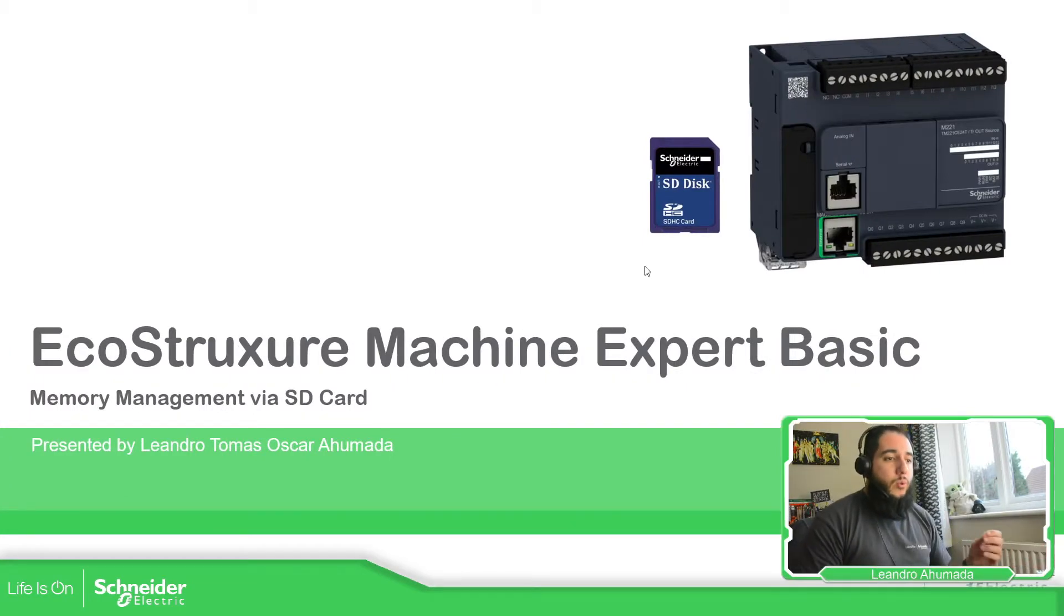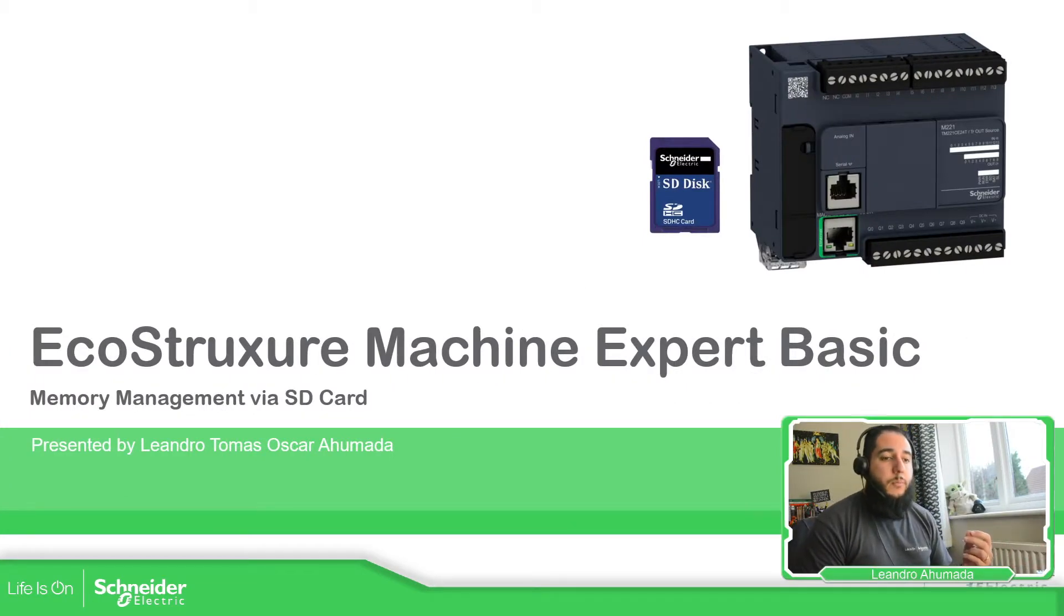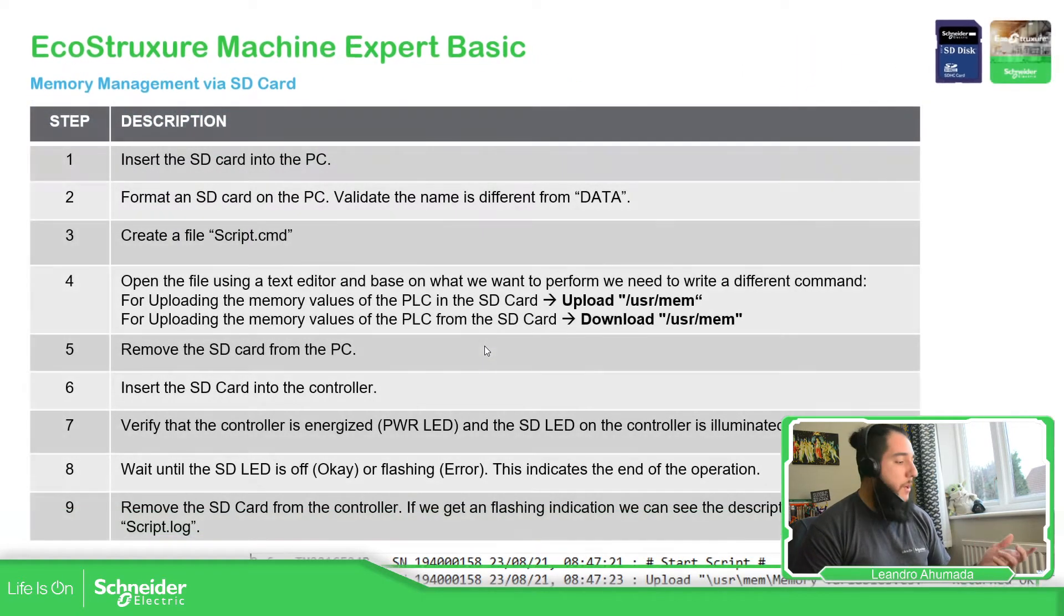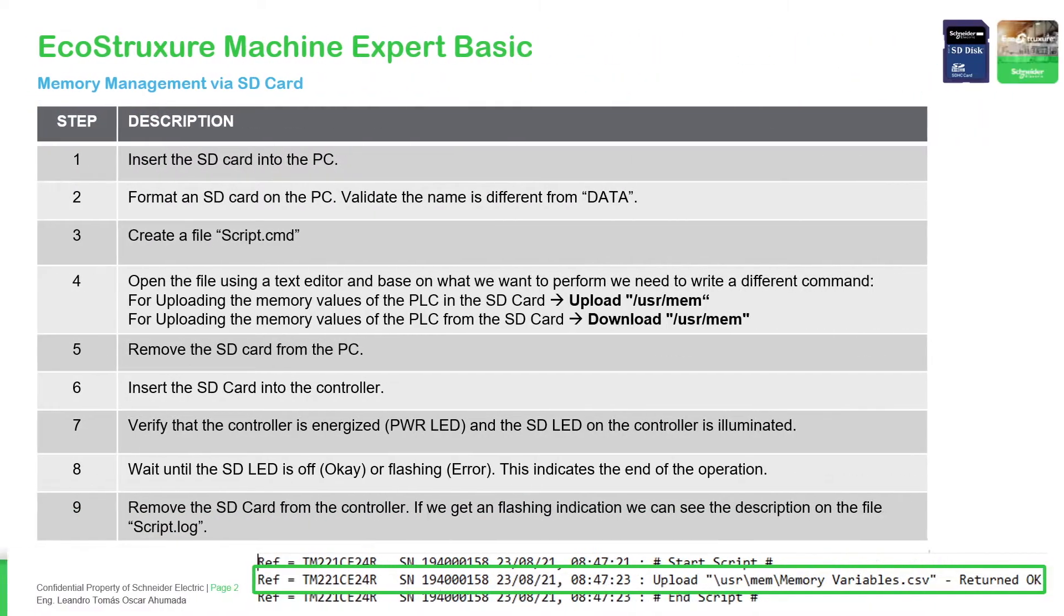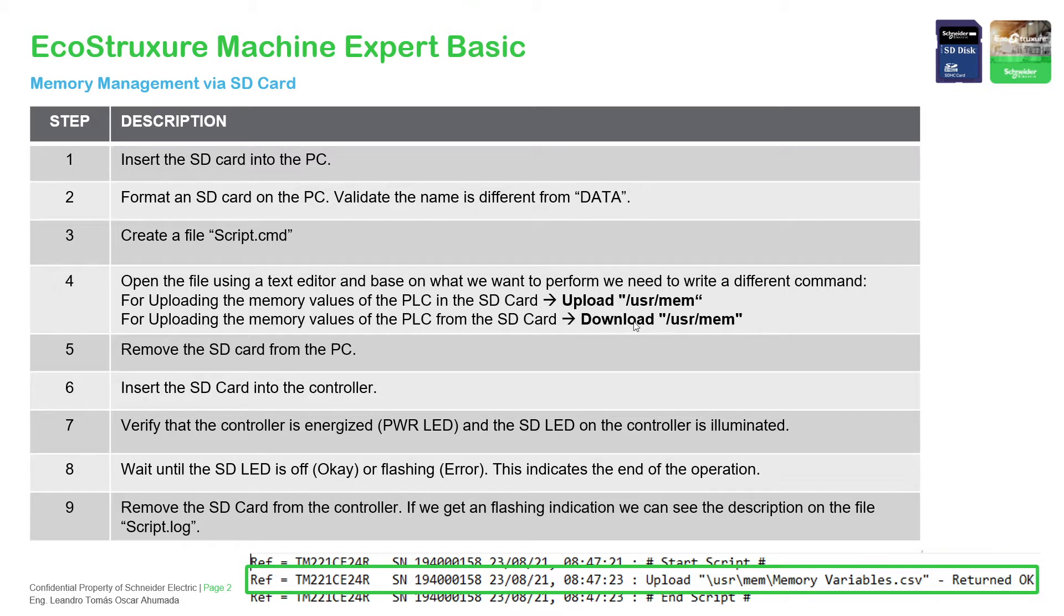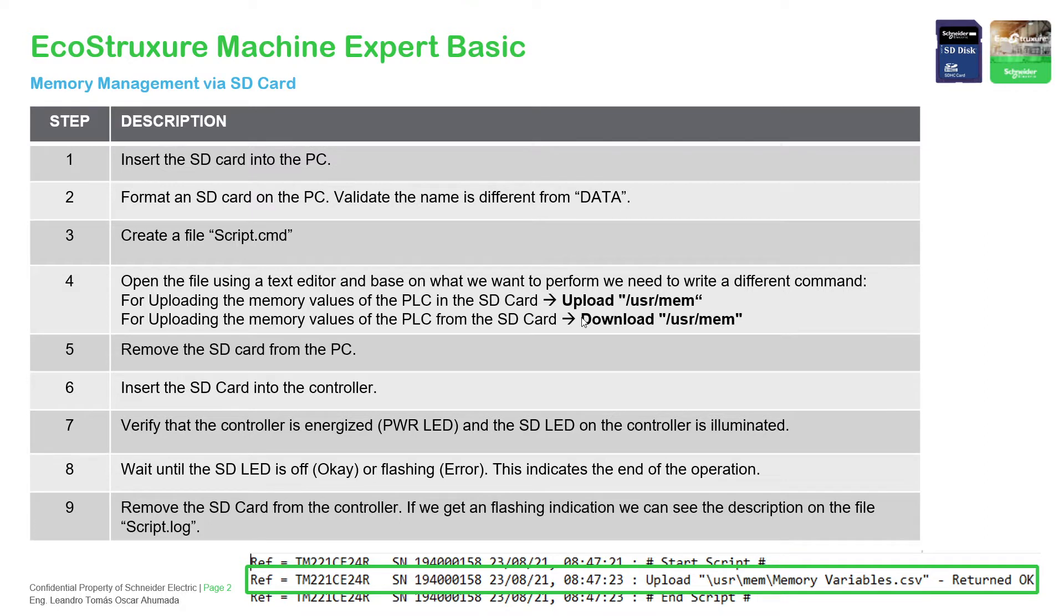In order to use the SD card it's very simple, we just need to follow these steps. We need the SD card, we need to create this file and a script, and then depending on the action that we want we can use upload or download. Upload the information from the PLC, we need to write this command. If you want to modify, just use the download with this information, then put the SD card in the controller and wait for the operation to finish.